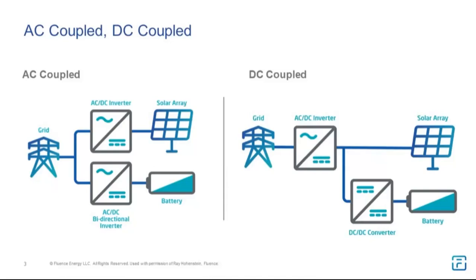I'd point out too that, in my view, that inverter should always be bidirectional. There's not a significant cost differential between a bidirectional and a unidirectional inverter like you'd use for a standalone PV plant. In fact, I'd go so far as to say you're doing a disservice to the grid if you don't use a bidirectional inverter there. We'll talk briefly about why people might be tempted not to, because of the investment tax credit, but I don't think that's really a valid reason.